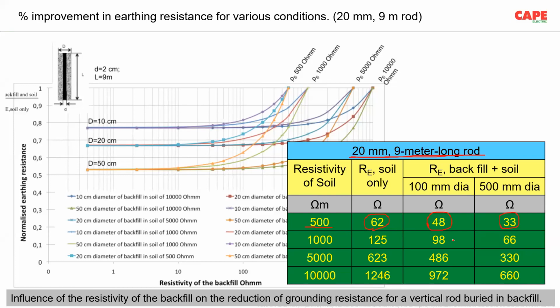So practically, filling the whole area with 500 millimeters of the earth enhancing compound will be a very expensive measure. Instead, you can add 2 more earth electrodes a little bit away and you get the same result. So basically, these materials also have a lot of limitations. Don't think that a chemical will solve all my problems. No, it is not like that. The chemical, depending upon the area which you are filling, 100 millimeter average, you get about 20 or 22% improvement, irrespective of whether you are using X make or Y make.